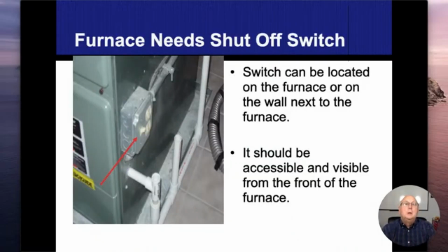Right. Shut-off switches, like I said, they should be in the same room wherever the furnace is. I kind of like them mounted on the furnace myself. It kind of verifies that the furnace is also grounded when it's connected to our conduit system and our junction box and so forth that's on there. To me, it's just a smart way to protect it.